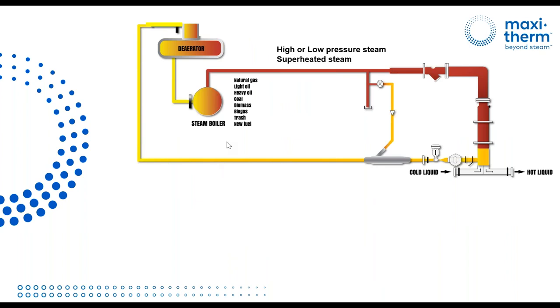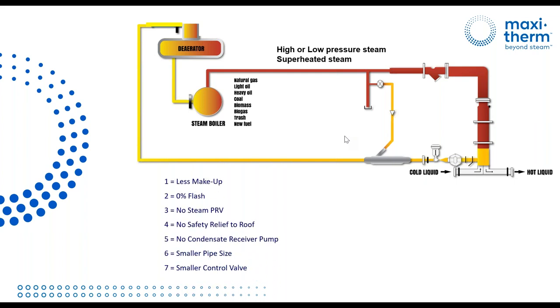Okay, so this is the 100% closed loop. When you use a flooding design, you will need less makeup water, zero flash loss, no more pressure reducing valve station, no more steam safety relief valve to the roof, because we rate the whole skid based on the safety valve set point on the steam boiler. The steam boiler safety valve set point at the other end is 300 pounds. We're going to rate the whole skid for 300 PSI. Yes, we can use superheated steam as well. No condensate receiver pump, as long as your steam pressure is higher than your condensate back pressure, no pump.